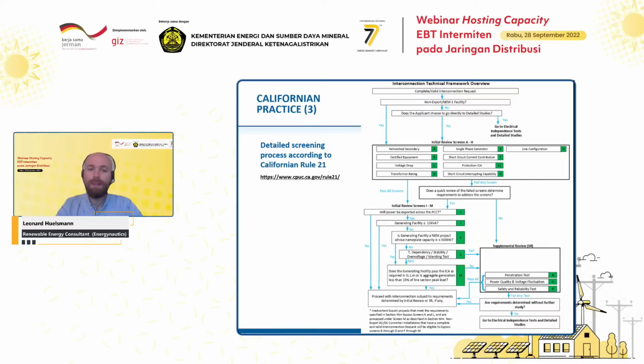What I want to make you aware of is that in most other regulations, and what is becoming common practice around the world, you don't limit every single PV system to a certain size. It's much better to define the maximum capacity that can be added to a specific distribution feeder, and allow PV systems to be added as long as this maximum limit has not been reached. Only if you get above it do you need to limit the PV capacity, or apply some mitigation measures.